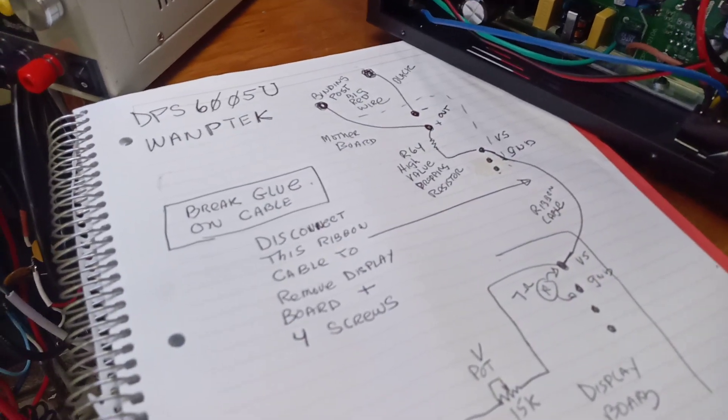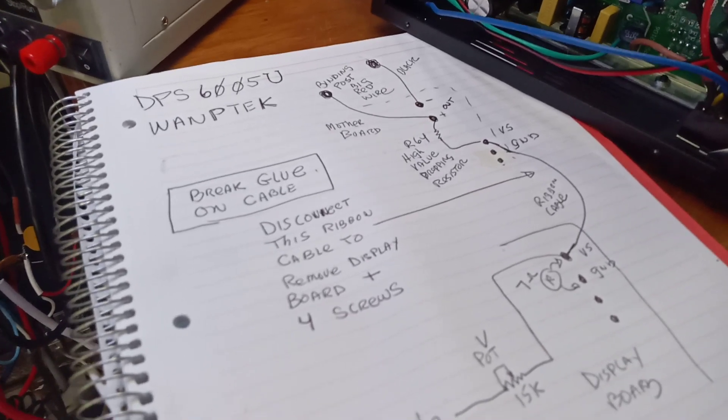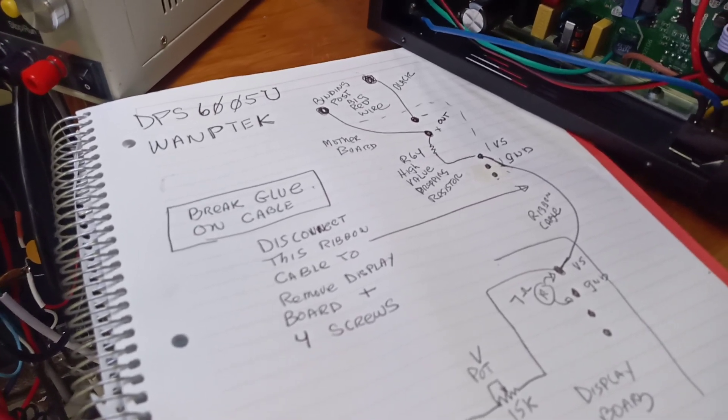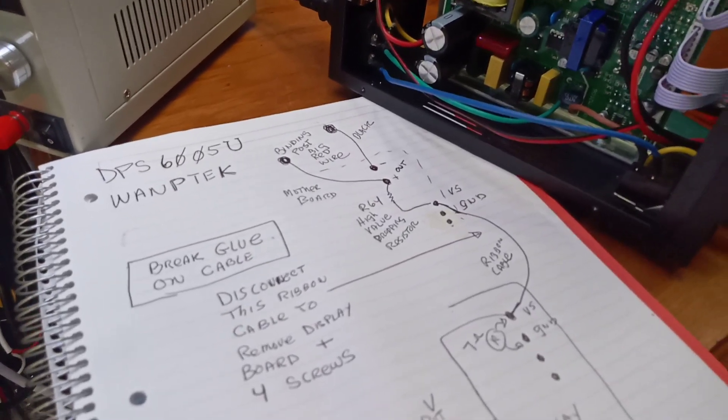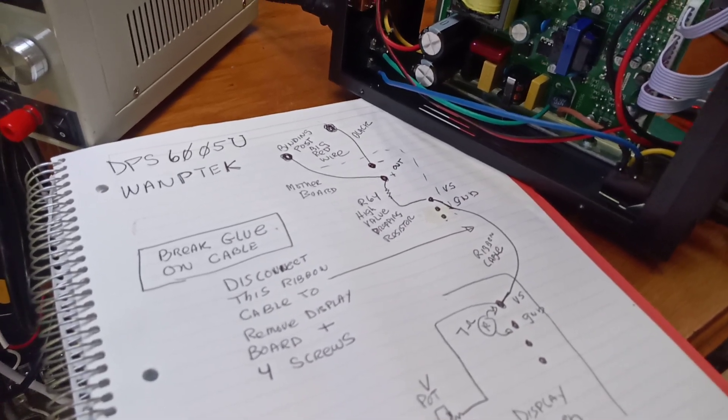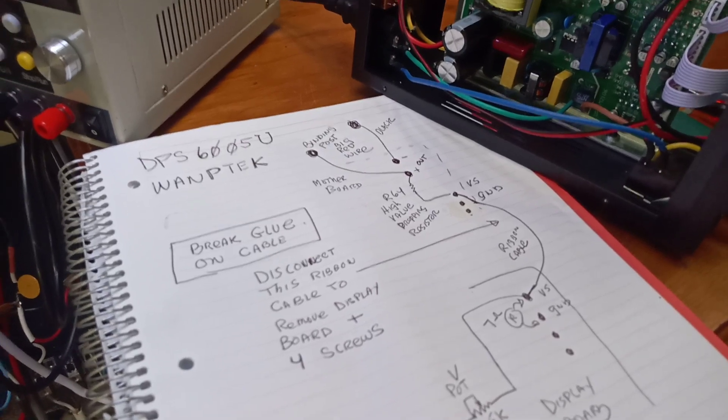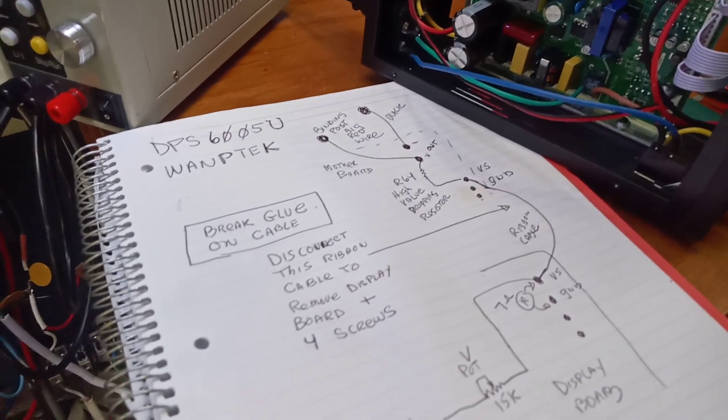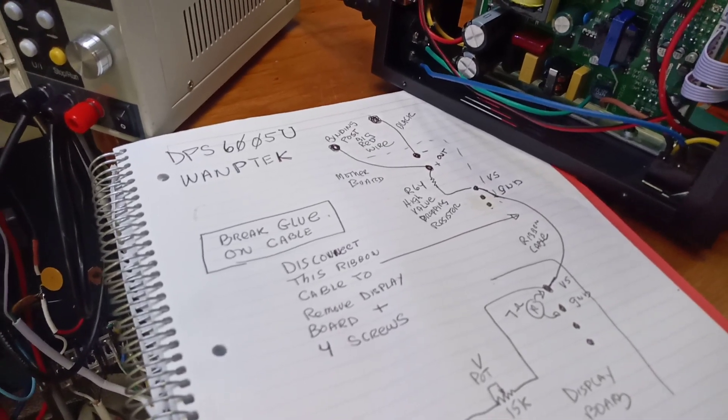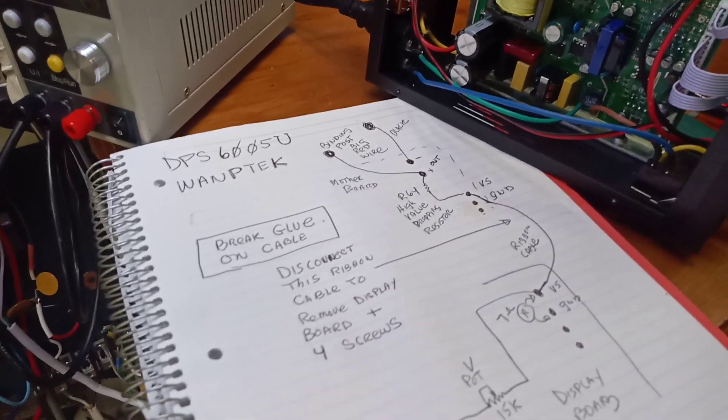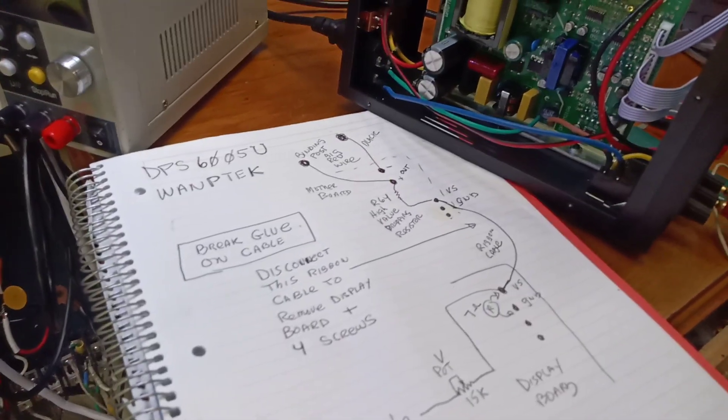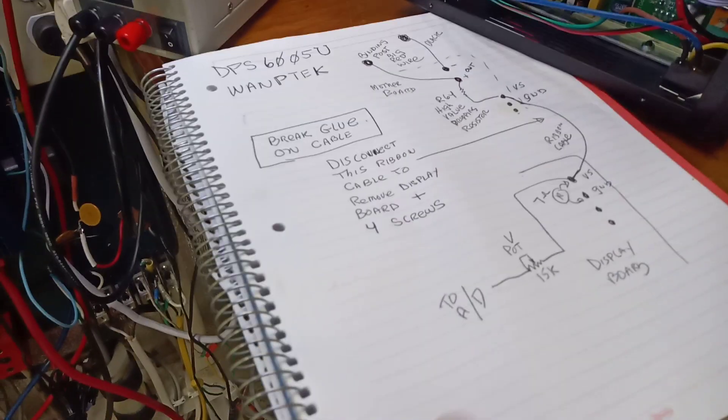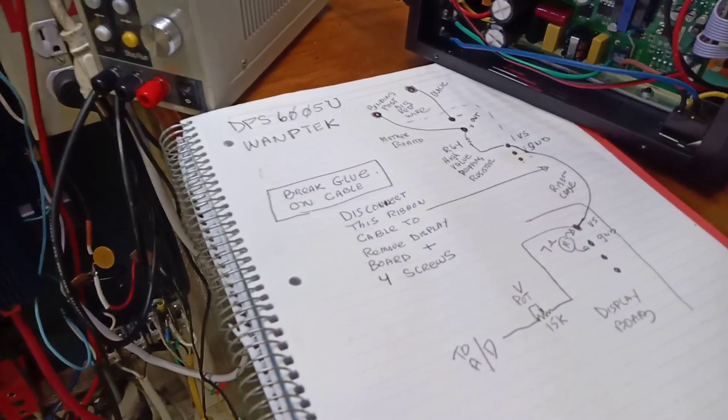So I decided I'd pull out the display board. I tried wiggling around the connectors to see if maybe that would do something, and it didn't. But once I pulled out the connector on the display board, it has a little bit of a glue attachment on it. And so you have to go in there with a screwdriver and sort of break that film, and then you can pull it apart. Well, once I pulled it apart, it wasn't shorted anywhere. So this thing came from the factory. They were able to adjust it up because the calibration pot, which is on the display board, I didn't have to change that one bit.